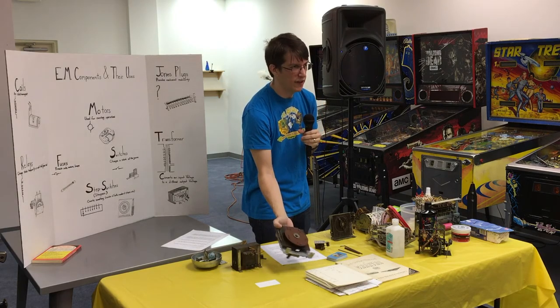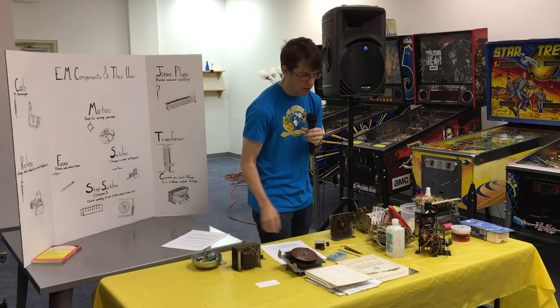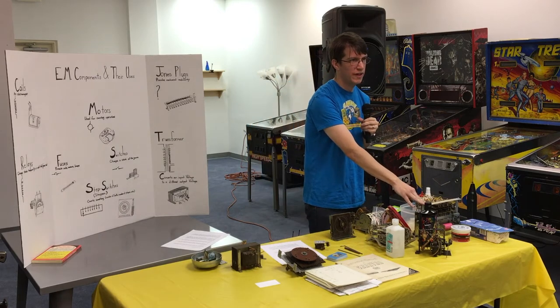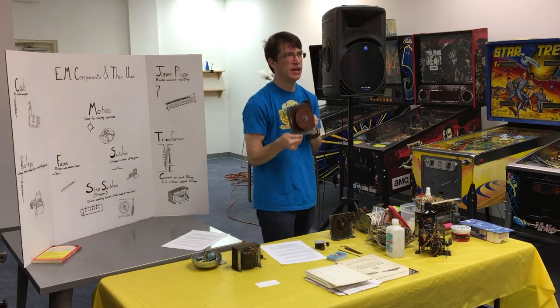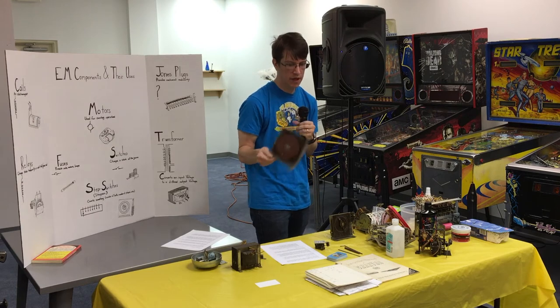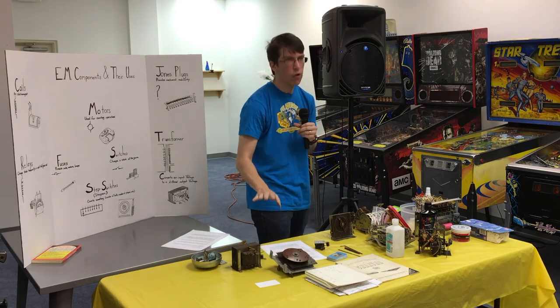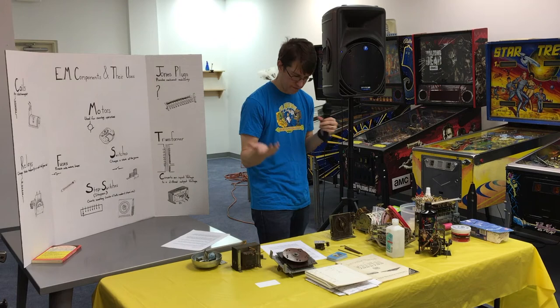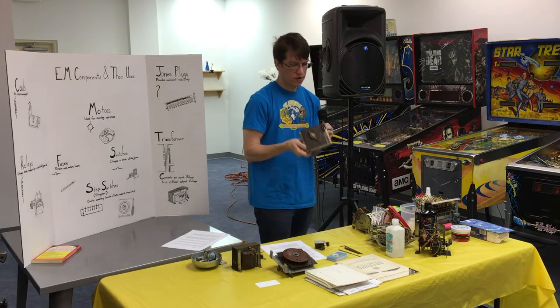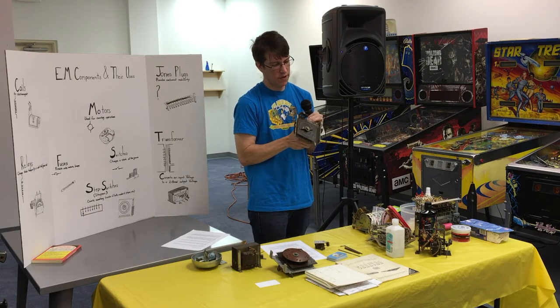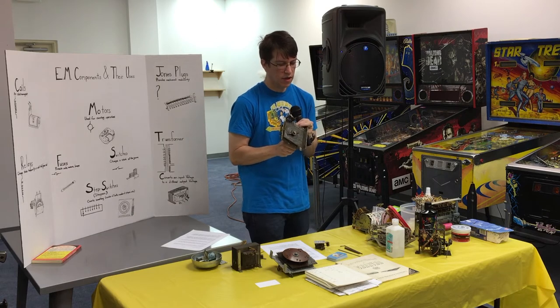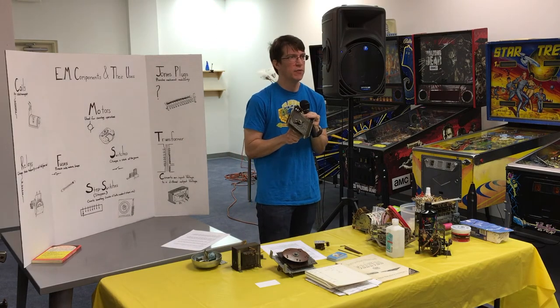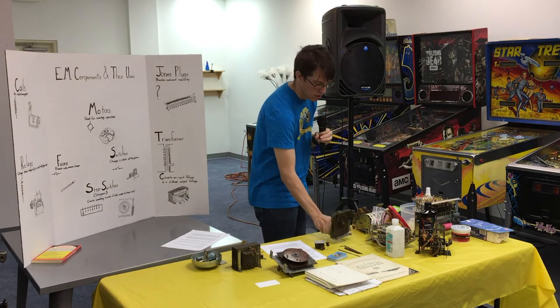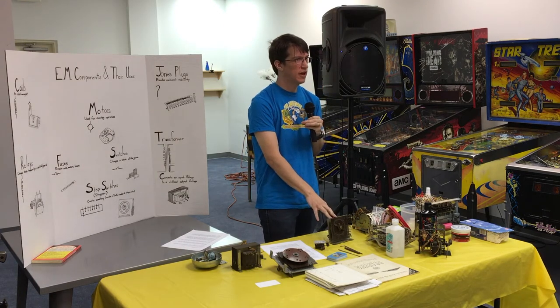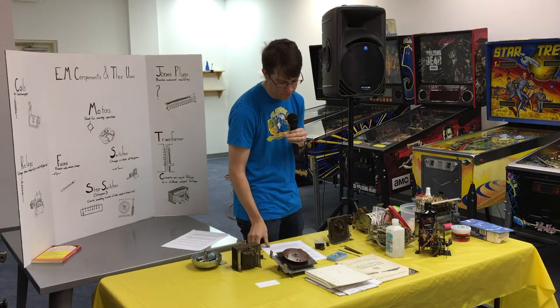It's like a rotary relay, or a trip relay, because it remains in that state until that coil is pulsed again. There's nothing to hold it there - you just pulse it, it moves, it moves on. This is a different type of stepper. These have been in use for a very long time, since the 1930s. They were used clear up to the 1970s, all the way to the end.